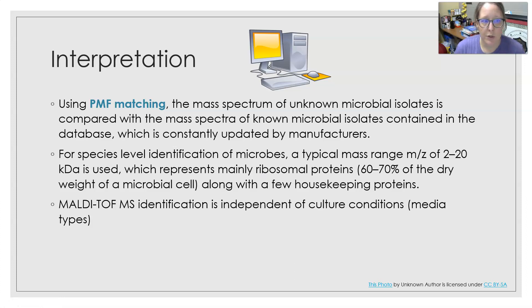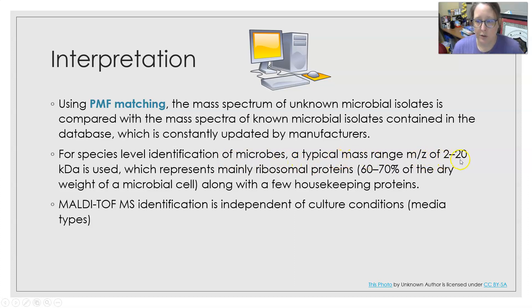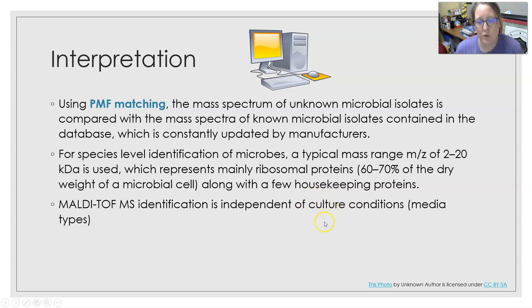For interpretation, using PMF matching, the mass spectrum of an unknown microbial isolate is compared with the mass spectra of known microbial isolates contained in the database, which is constantly updated by manufacturers. For species-level identification of microbes, a typical mass-to-charge ratio range of 2 to 20 kilodaltons is used, which represents mainly ribosomal proteins — 60 to 70 percent of the dry weight of a microbial cell — along with a few housekeeping proteins. MALDI-TOF identification is independent of culture conditions, so it doesn't matter what type of media the bacteria was grown on.